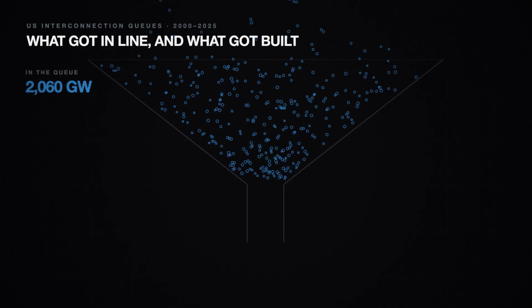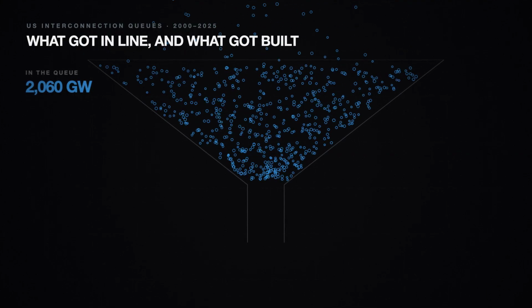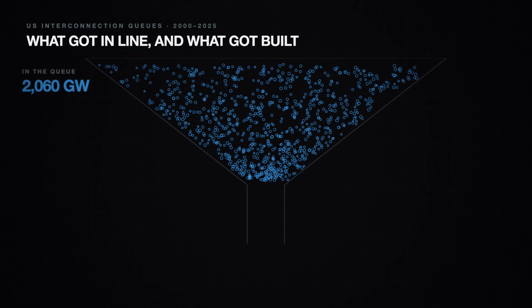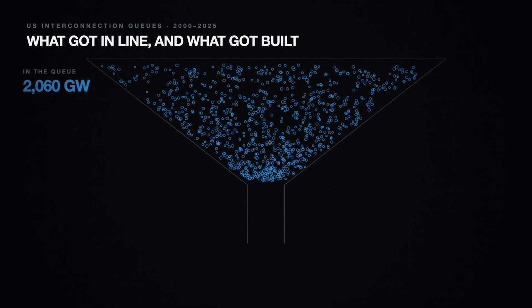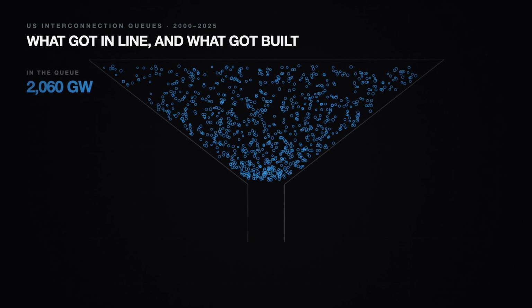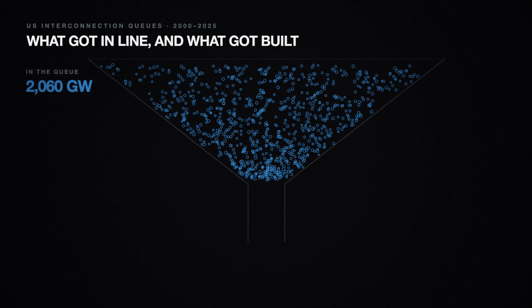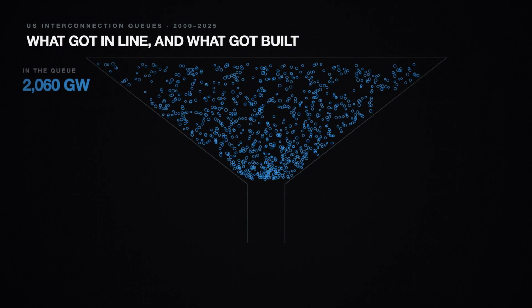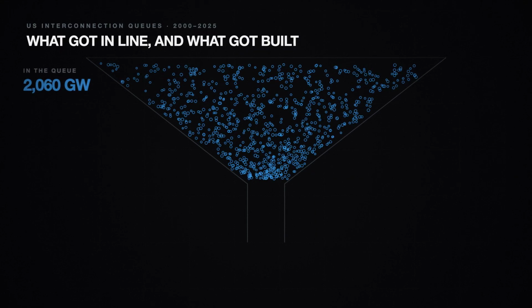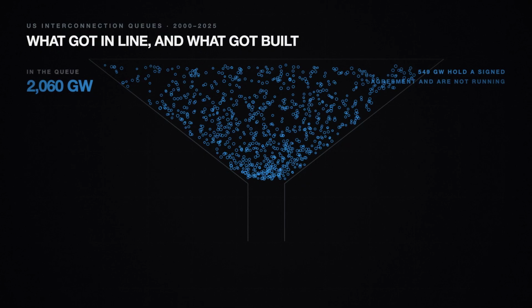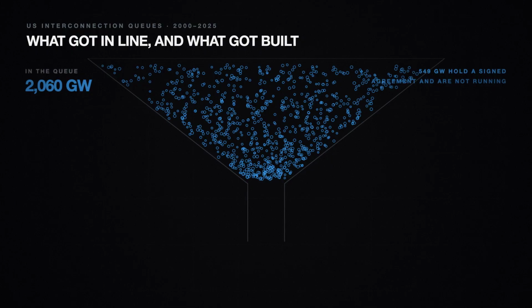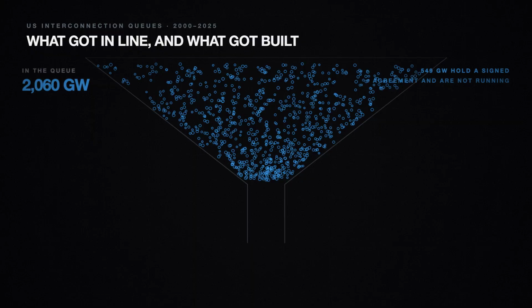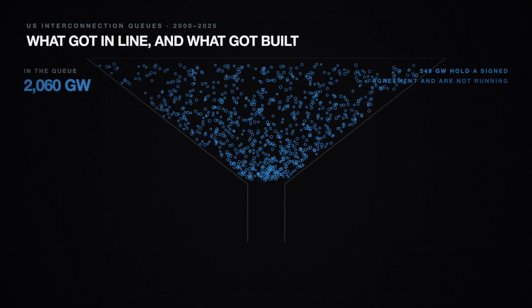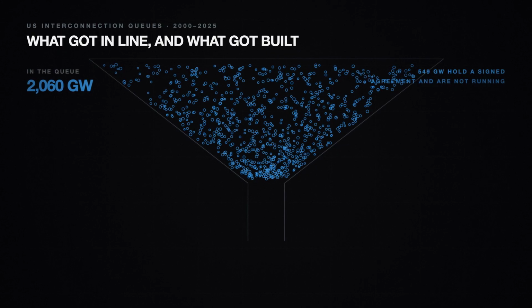If the demand is uncertain, what about the supply? Here the numbers look magnificent. At the end of 2025, more than 2,060 gigawatts of generation and storage were actively waiting to connect to the American grid. For scale, the entire United States generating fleet is about 1,300 gigawatts. There is, apparently, more than 1.5 times the existing grid queuing up to join it. 549 gigawatts of that has already signed or drafted an interconnection agreement and is simply not operating yet. So the obvious conclusion is that the supply problem is solved, and the only issue is paperwork.